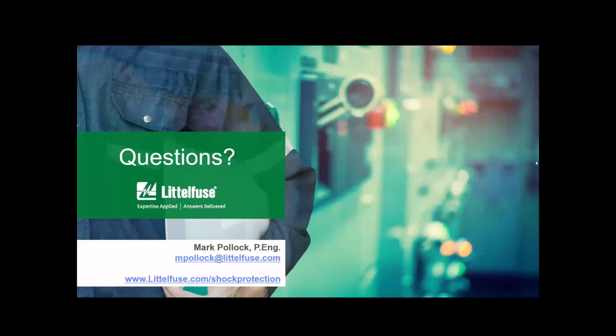I see one relative to the ground monitor circuit, distinguishing between a good equipment ground and a secondary ground. What I will say is the ground monitor circuit is designed to make sure there is a low resistance path from the frame of the device that's being powered, back to the power system. So if there are parallel electrical paths that exist through other things other than the equipment grounding conductor, it is potentially possible that those could be part of the measurement. It may not be possible to have that as fully isolated, but the fact remains that it is still verifying there is a low resistance path, which will still have the net effect of providing that protection to ensure there is a low touch voltage on the frame.